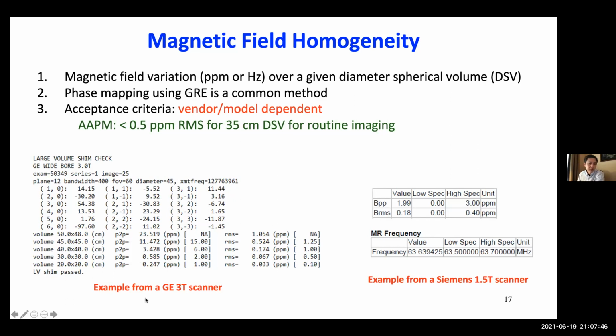So on the left-hand side is an example from a GE 3T scanner. You can see they look at different spherical volumes: 50 diameter, 45, 40, 30, 20, and measure peak to peak and root mean square. Here it also lists the limit. So for example, for 30 centimeter diameter, the measurement was 0.067 ppm, and the criteria is 0.5 ppm. This is very close to the recommendation by the AAPM. On the right-hand side is an example from a Siemens 1.5T. They don't provide measurements at different diameters, but they use a fixed phantom, the same phantom every time, and measure the homogeneity within that phantom. In this case, the peak-to-peak measurement and root mean square measurement are both listed, and this is the criteria.